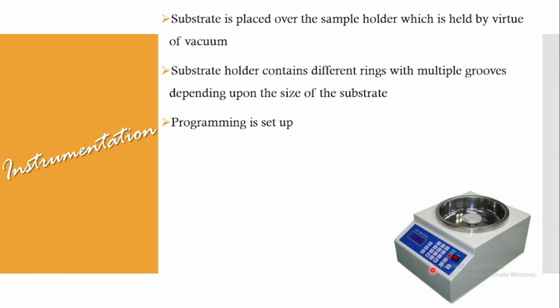So whenever the deposition of thin film is taking place, we have applied certain speed and acceleration to the coater, and suddenly if it stops abruptly, it is going to harm the quality of the thin film. So this ramp down step, which is another setting in some of the spin coaters, ensures that the spin coater will stop very gradually and not suddenly. So these are some of the programming which will be with respect to different softwares corresponding to different instruments.